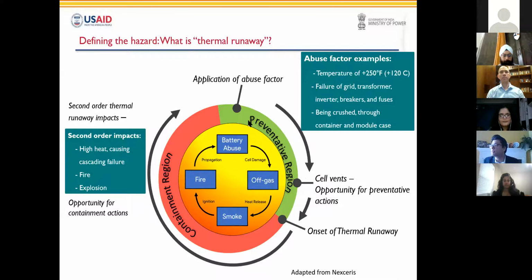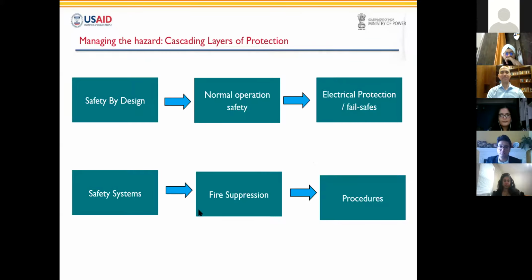Essentially, if the abuse condition is removed in this region, then you can stop the battery from going into thermal runaway. Once thermal runaway starts though, design standards require that several suppression and containment procedures be designed and initiated. It also requires that the abuse is not propagated. Now, what are these design standards? The number one is cascading layers of protection, or concentric layers of protection. Energy storage systems are recommended to follow safety by design philosophy. They are required to have concentric layers of protection.